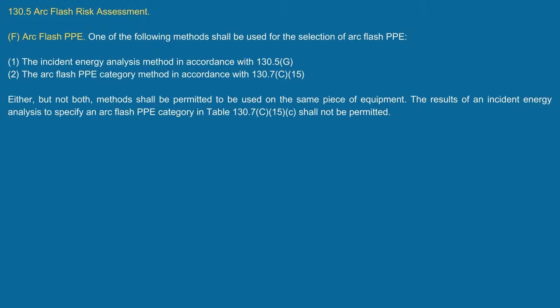Okay? Gotcha. And then it tells you either, but not both, methods shall be permitted to be used on the same piece of equipment. So you can use either one. We don't care which one, but it says the results of an incident energy analysis to specify an arc flash PPE category in the table, guess what? Is not permitted. The reason is that we have certain tasks, and we built a lot of extra safety in there, I guess you could say. When you look at that, it's based on certain parameters. That's why you can't use the calculation method, because you're not meeting those parameters and the extra safety that we built into those tables.